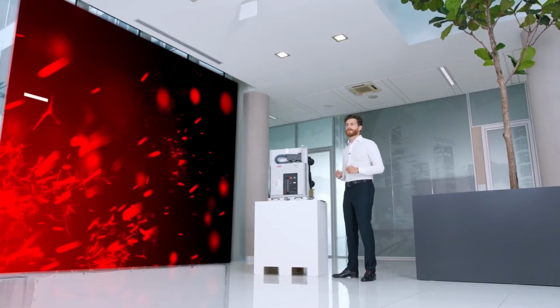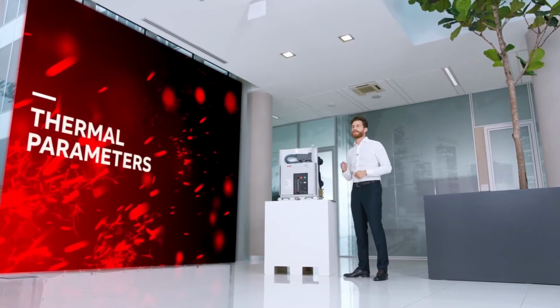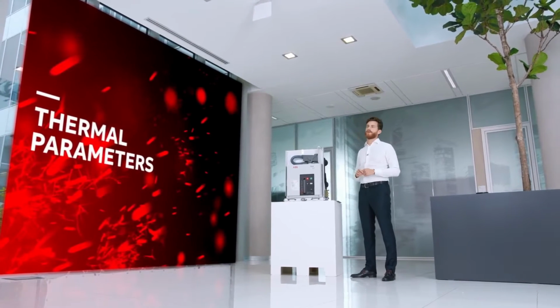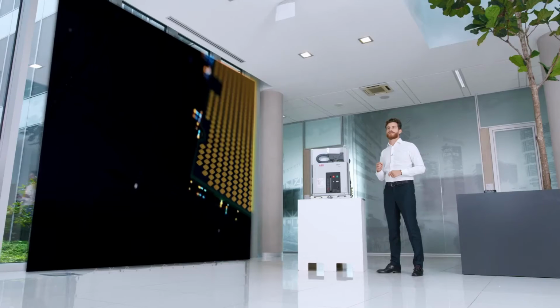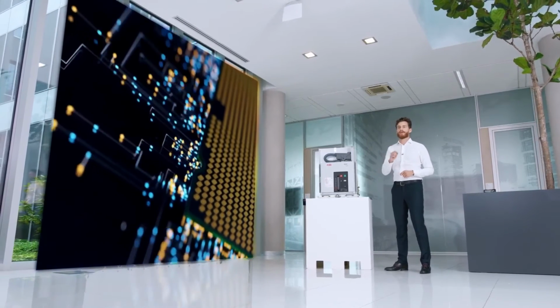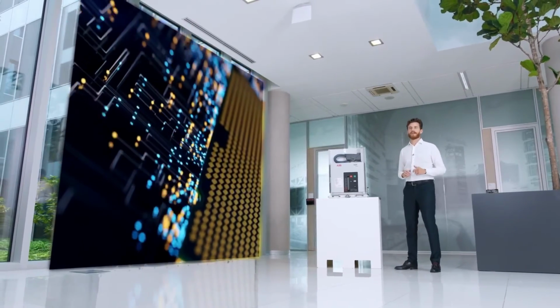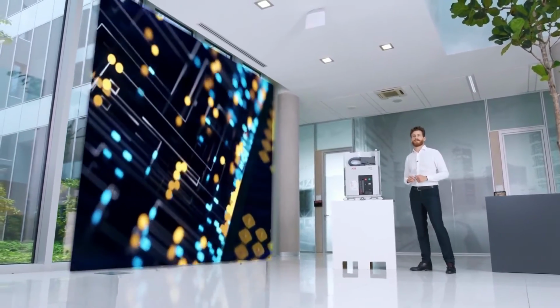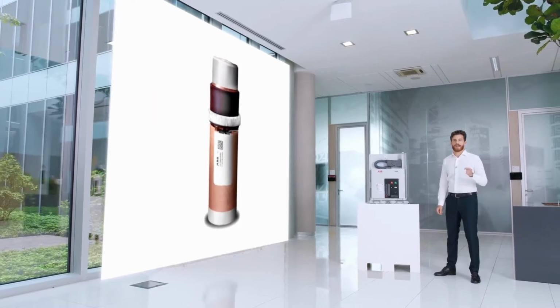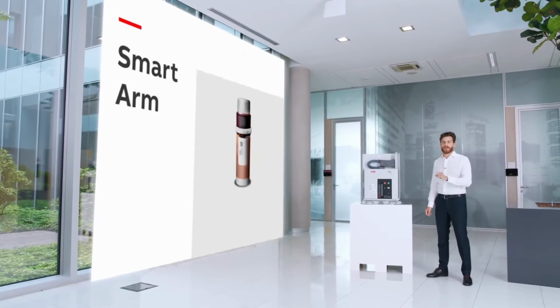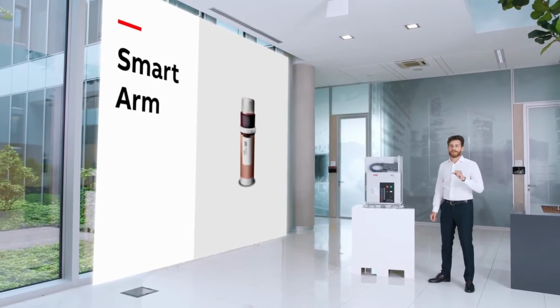First, thermal parameters. They can identify symptoms of bad, loose, or damaged connections, or even overloading. The circuit breaker and panel interfaces are key to ensuring nominal current flow with correct resistance and holding kiloamperes of peak current. Therefore, we designed an embedded sensor to accurately detect the temperature closest to this interface. This new solution, implemented in each of the 6 connection points, forms our smart arms.